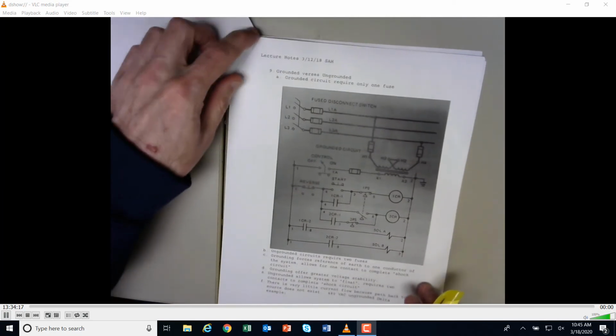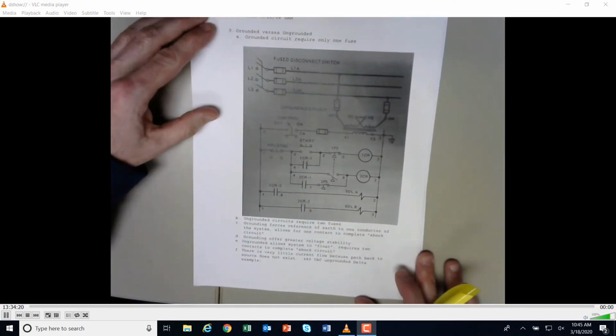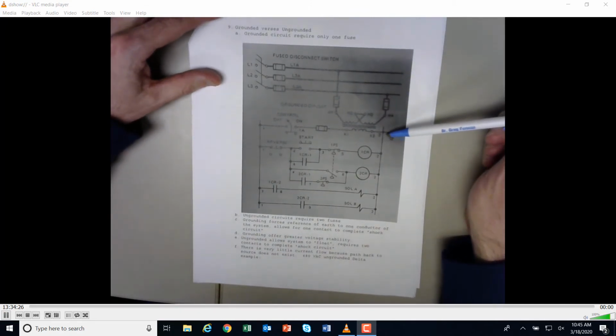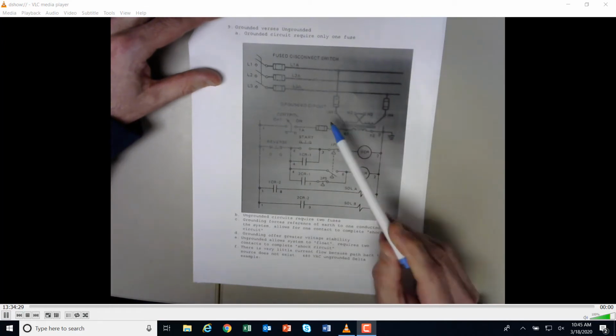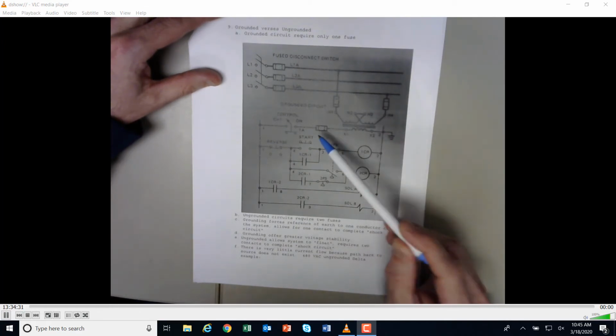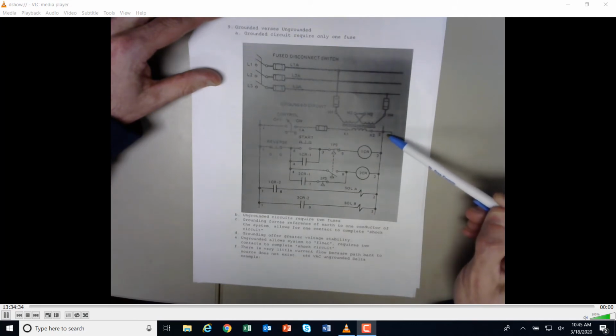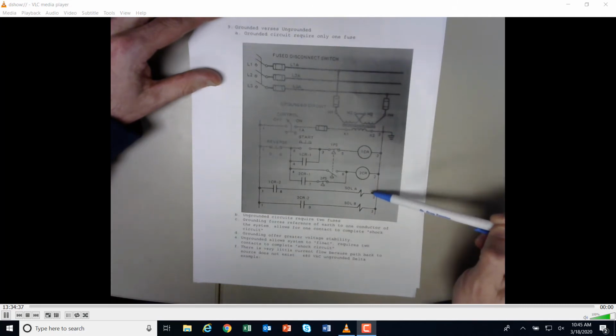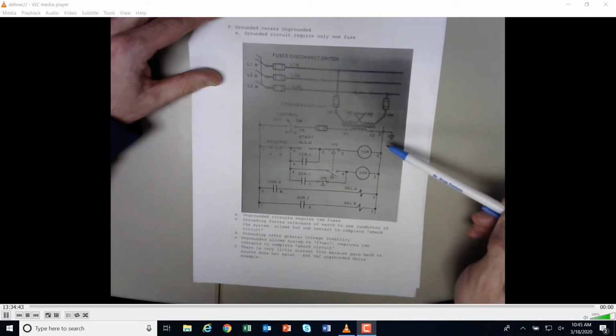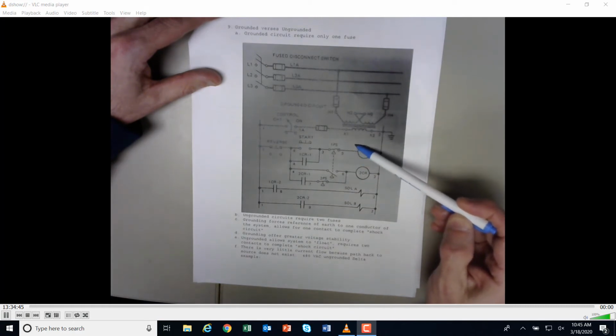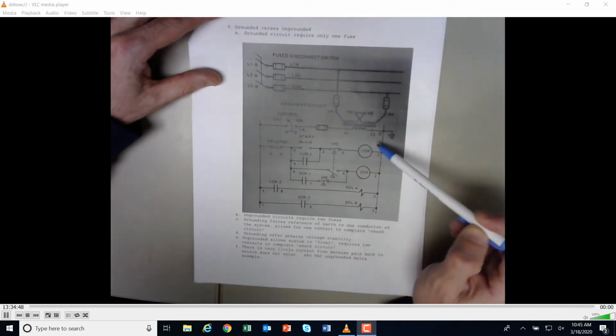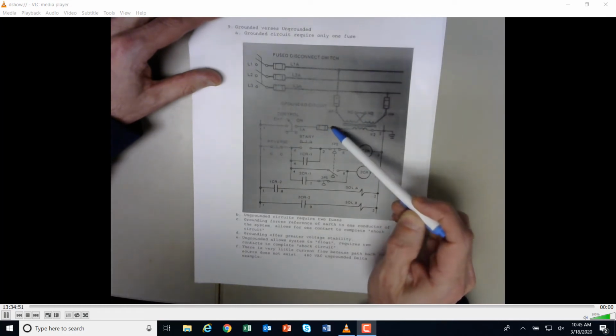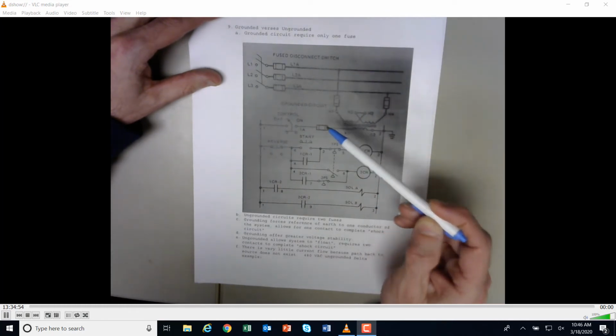We're going to take a look at grounded versus non-grounded. So here, I'm going to my next item, and what we have here is a grounded secondary. You'll see on the grounded secondary, there's only one fuse. The ungrounded, there was two. And this is an earth. So each side of these loads has a hard contact to earth. So if there's any short in here, this is going to go straight to earth. You're going to get a massive amp draw, and this is going to blow this fuse right here, okay?